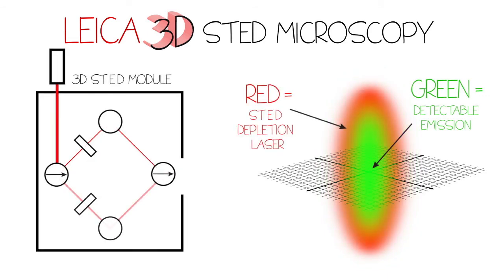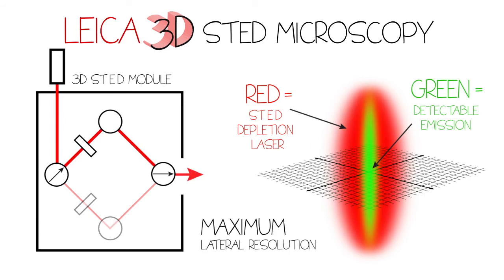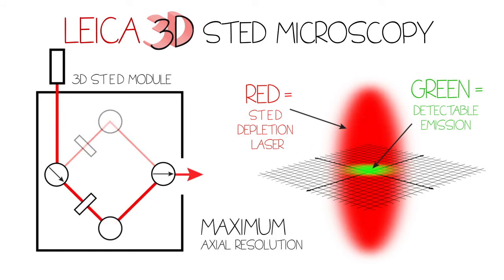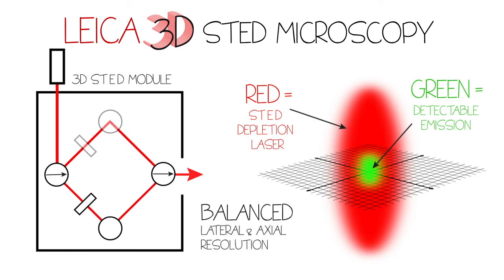Not only does STED improve resolution laterally, but axially as well. The 3D STED module allows you to tailor the distribution of the STED laser for the greatest lateral resolution or the greatest axial resolution. The balance between lateral and axial paths is tunable so that you can fully tailor your point-spread function in all dimensions.